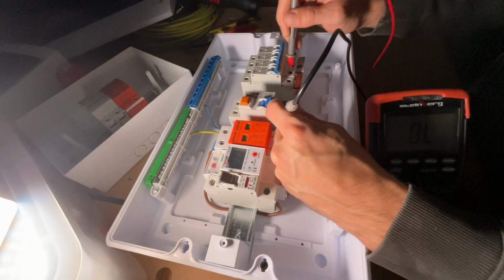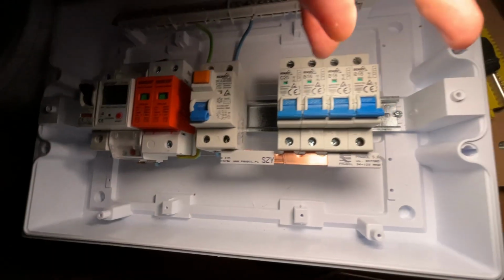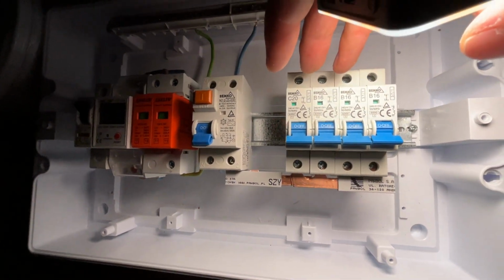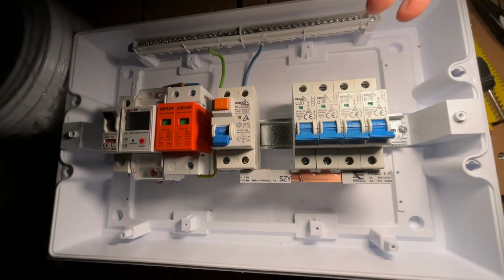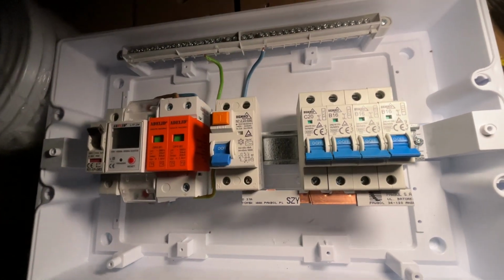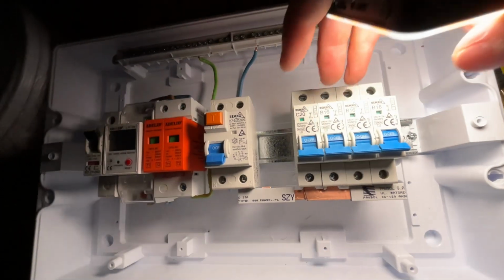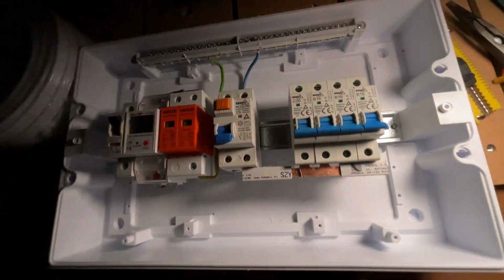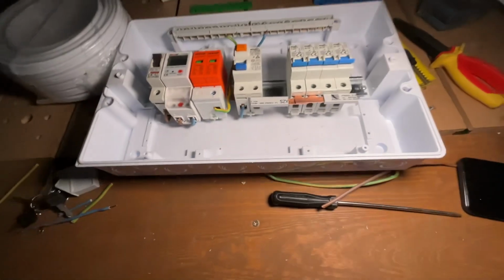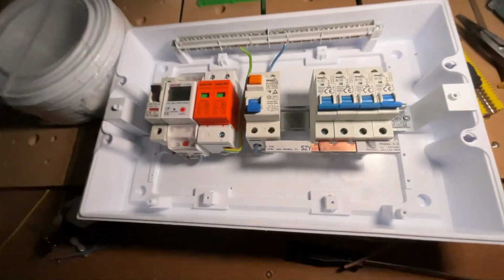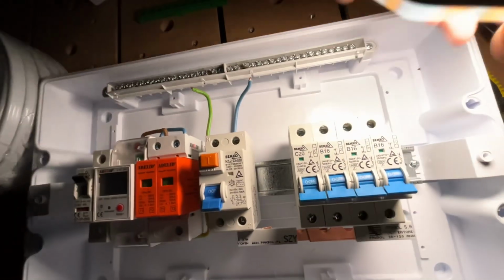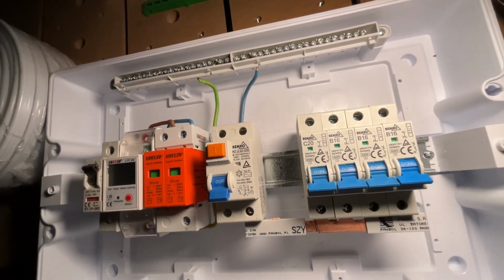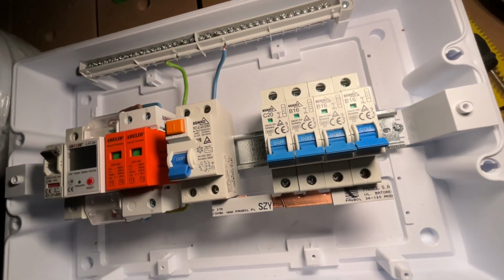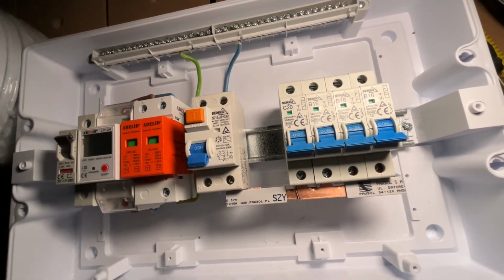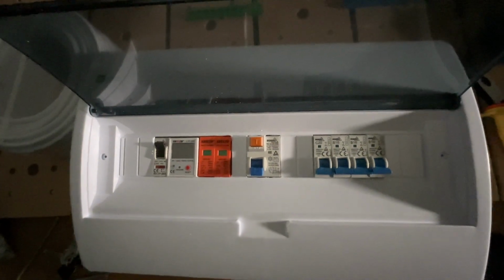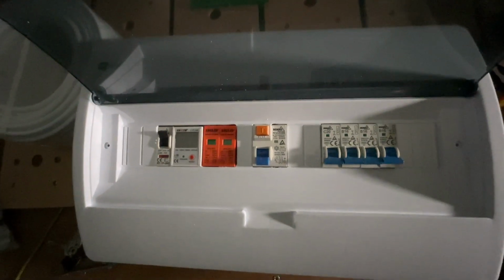Last but not least, we got overcurrent circuit breakers. This simply breaks after current in the circuit exceeds a certain amount. In most cases, 16 amps are used in home installations. Because there are different voltage and wire diameter standards across countries, you need to be careful while picking the right one for yourself. My AC installation is running on 230 volts, so 16 amps gives me around 3.5 kilowatts of power per circuit. If from one circuit I would want to drain even more power, this breaker will pop.